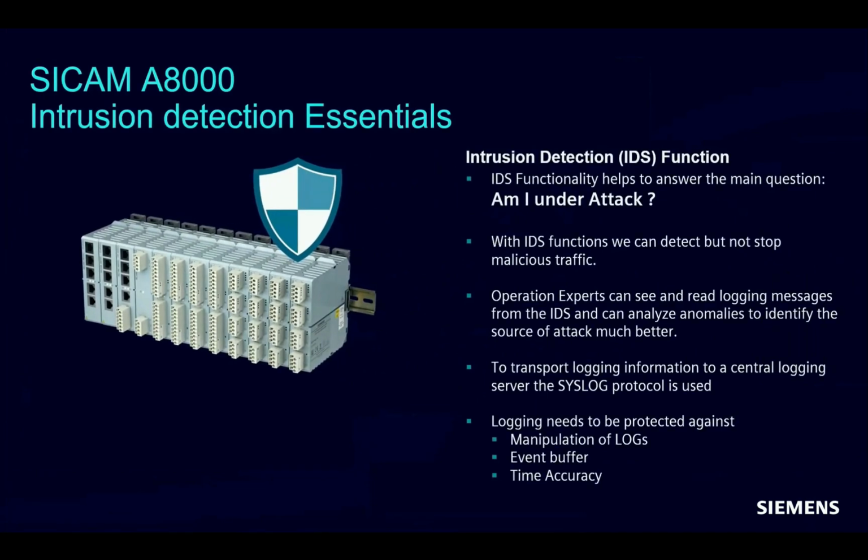The next cybersecurity-related new function is a new advanced intrusion detection functionality integrated in our Linux-based A8000 RTUs. In our standard security blueprint for a secure substation, this function is running, for example, on a dedicated router with next generation firewall and the integrated intrusion detection functionality. As not all customers are already investing in the 100% solution for a secure substation, or depending on the project size and the importance of the substation, a basic setup for security is sufficient. And this feature now provides a very good alternative for such use cases.